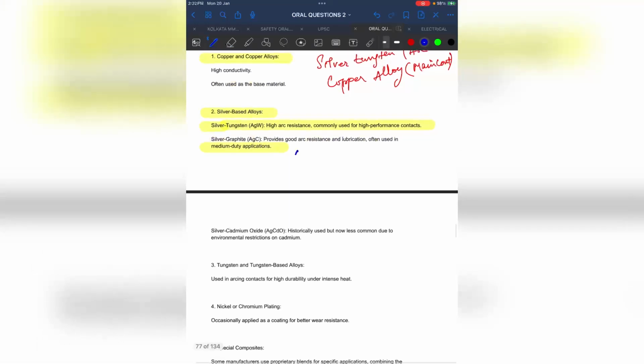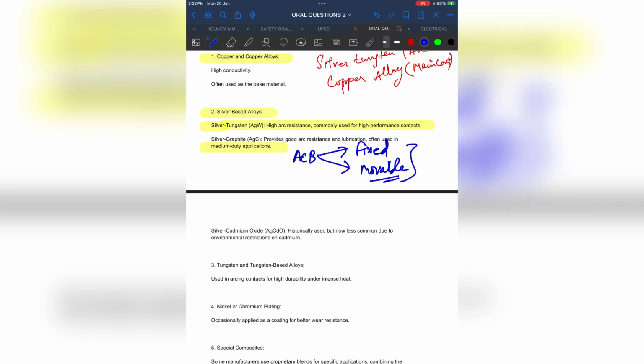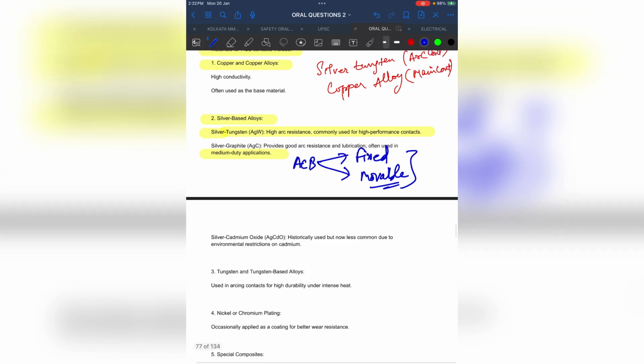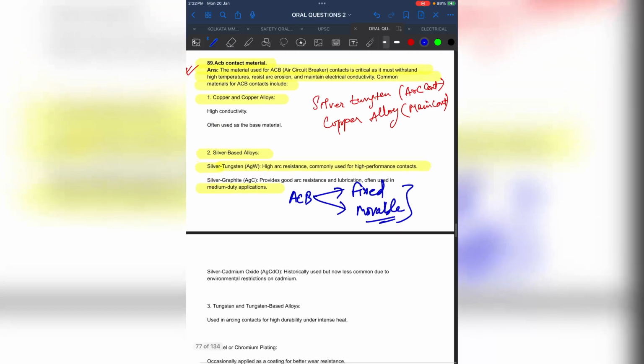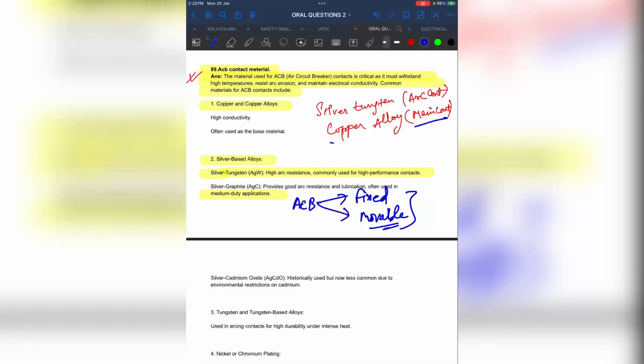Okay, so you know ACB has two contacts. One is the fixed contact and one is the movable contact. The fixed contact and movable contact have different materials. The main contact is made up of copper alloy, and the arcing contact is made up of silver tungsten. Why is the arcing contact made up of silver tungsten? Because it is highly arc resistant and can withstand high temperature.